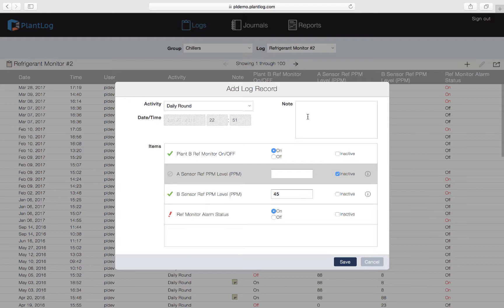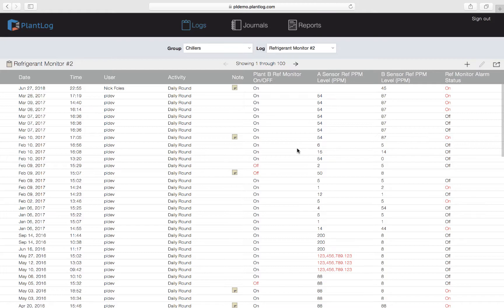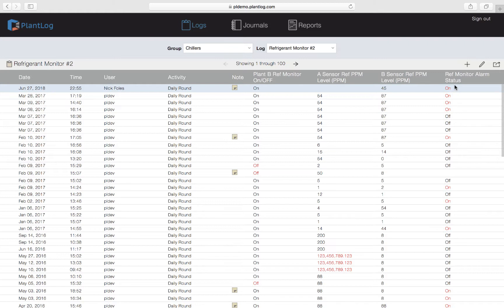There's also a note box in the upper right corner where you can add an optional note. If administrators have turned on the Force Note on Exception feature, you may be required to enter a note when certain exception values are recorded. Let's enter a quick note — 'This is a test for the video' — and hit Save. The record now shows up at the top of the list since records are in chronological order. The first reading was On, the second was set to Inactive so it's blank, the third was 45 PPM, and the last — alarm status On — shows in red as an exception.